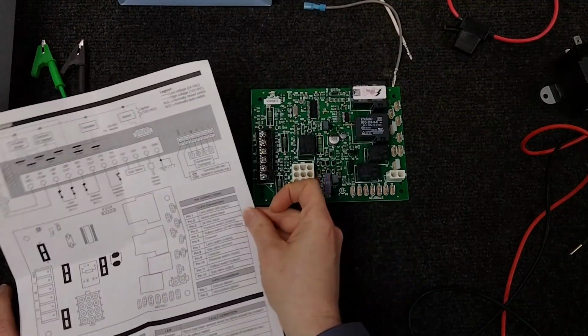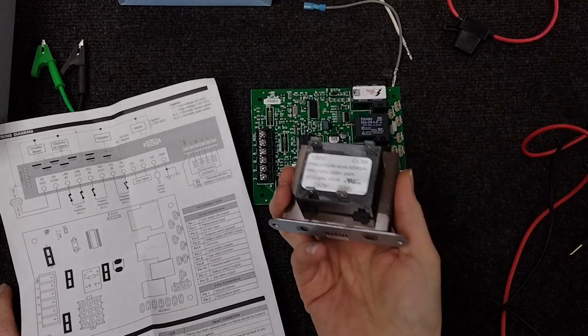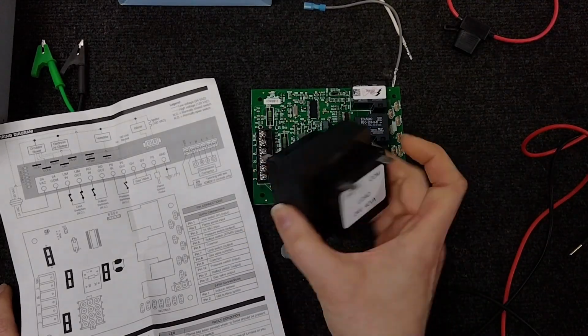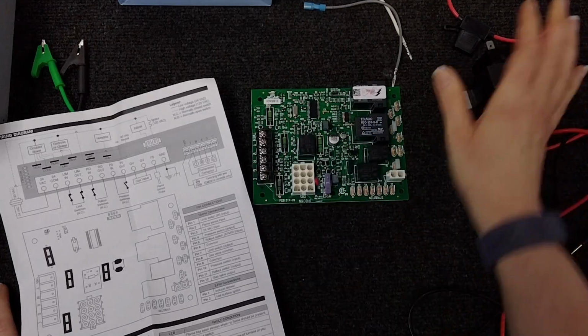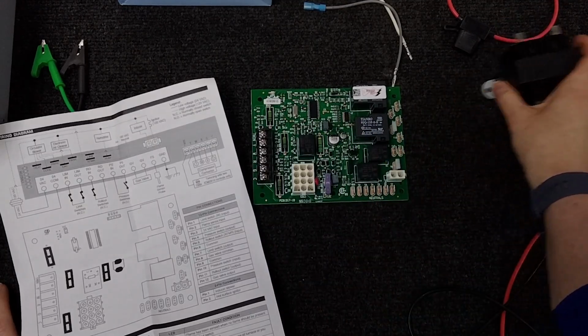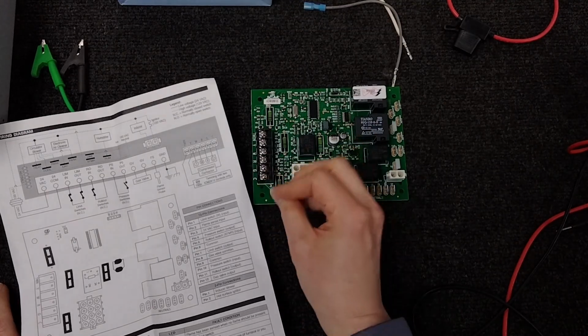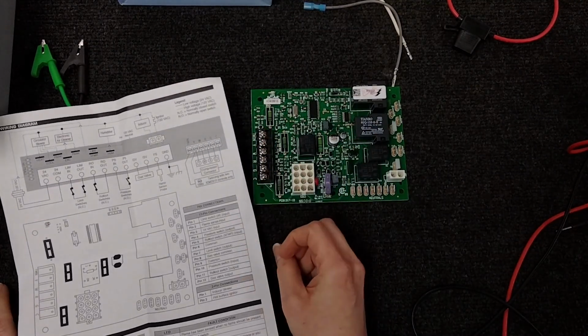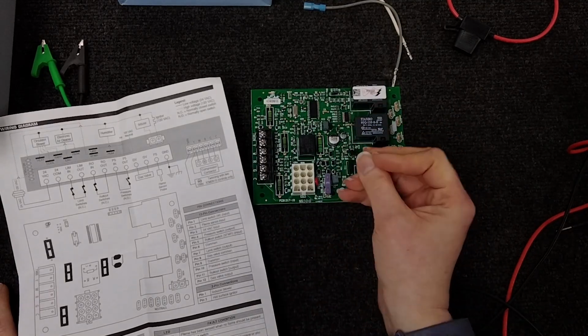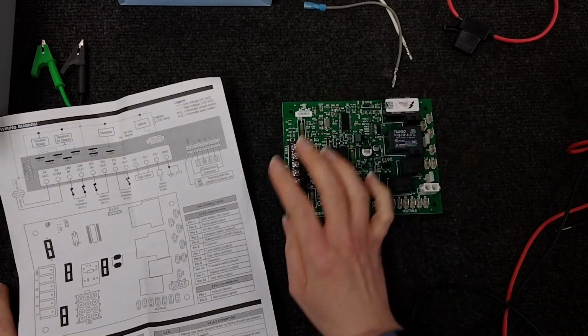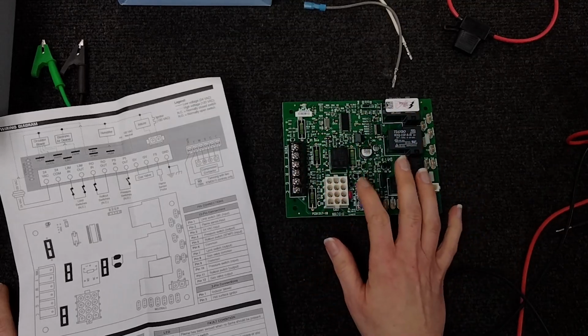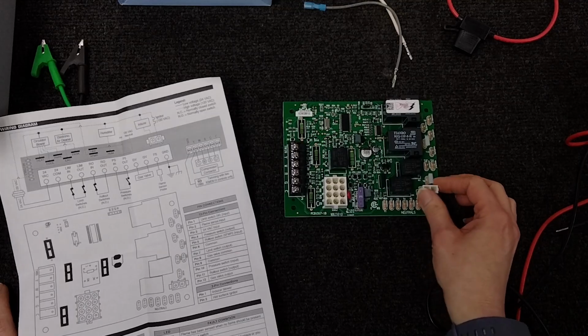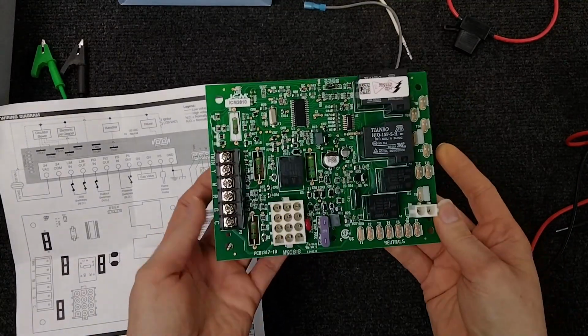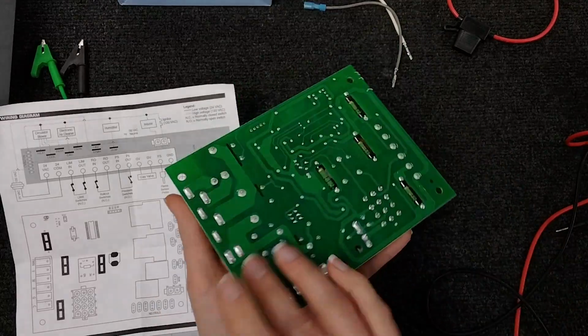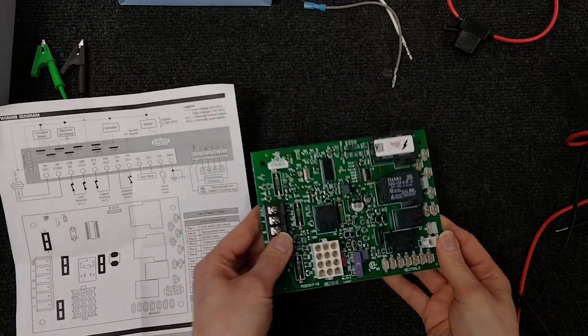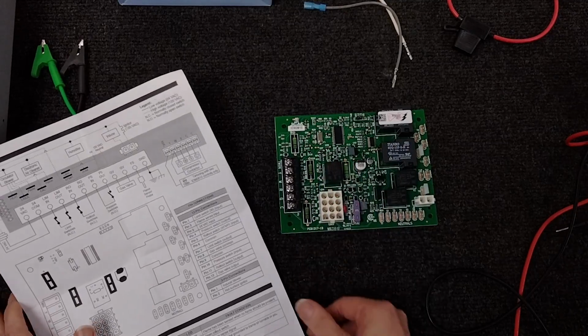So let's break that down a little bit. We know from our transformer that it is sending the 24 volts. We know that's good. We can rule that out. And then we know that our thermostat is sending voltage to call the heat at the unit, but there is no light on this board. And the newer boards, you can't see the lights on these because they're itty bitty LED lights in here. But yeah, in the older ones, you can actually see those bulbs sticking out.